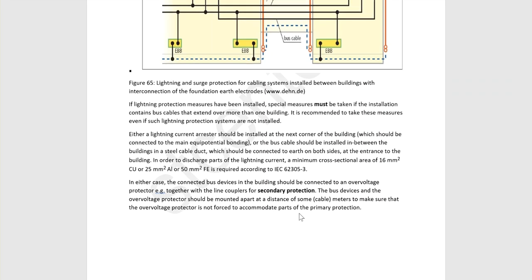Okay. In either case, the connected bus devices in a building should be connected to an overvoltage protector together with the line couplers for secondary protection. The bus devices and the overvoltage protector should be mounted apart at a distance of some cable length to make sure that the overvoltage protector is not forced to accommodate parts of the primary protection.